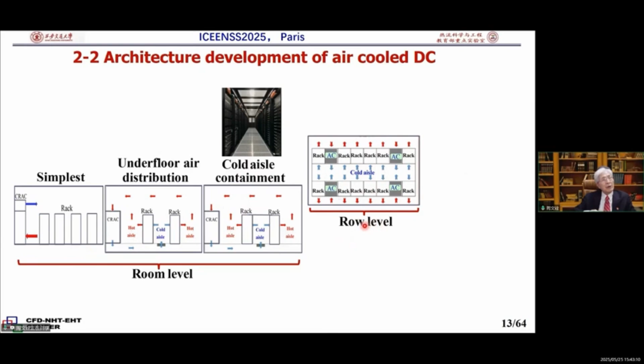Now, the further step is the rack level. That means each rack has a closed air cooling loop. Hot air goes into the back of the rack where it is cooled by a heat pipe. Then when it goes out of the rack, it becomes cold. Then it recirculates to the inlet again. So for this kind of rack cooling, the mixing between hot and cold air is very small. So approximately SHI equals 0 and RHI equals 1. So this is called rack level.